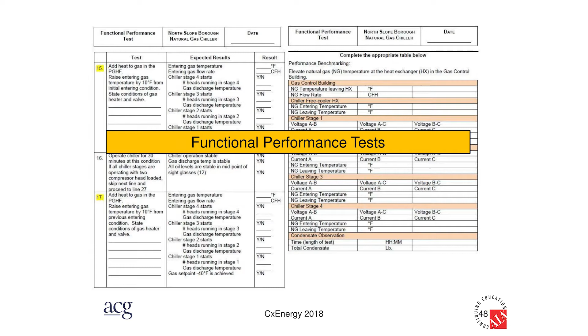What you're looking at here, this is the primary gas handling facility, and this green actuator is controlling a 3-way valve from the boilers. When the gas comes in the wintertime at 900 psi and 30 below zero, and then goes through a pressure drop to 300 psi, it drops in temperature quite radically, and it can become so cold that it can freeze up seals and actuators on other control valves. So they have to have a means of reheating the gas. We used that capability to impose artificial loads on the gas. And so when we were doing the functional testing, we tested it clear up to about 75 degrees incoming at full flow.